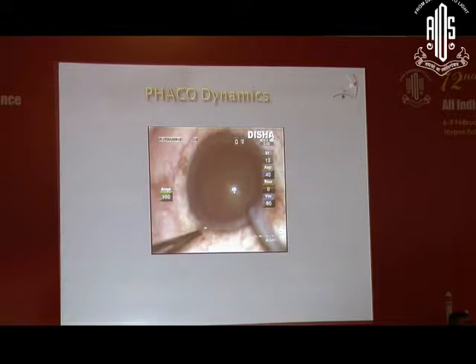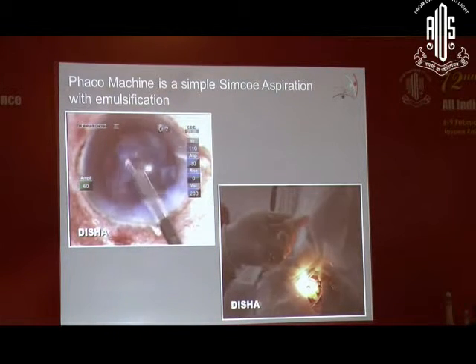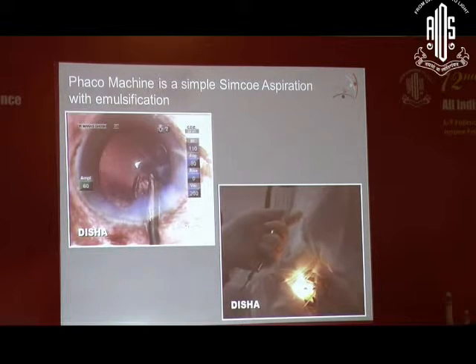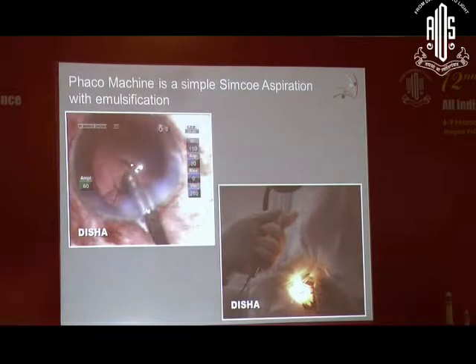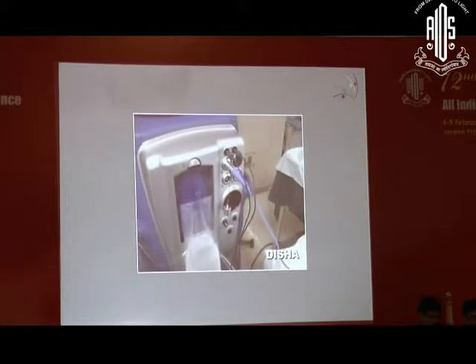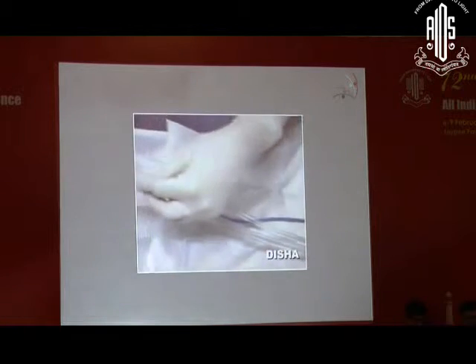The third area that I would like to take up with you is phaco-dynamics. We need to understand a little bit of this. Without complicating things, it is just an irrigation aspiration system where we have emulsification or ultrasound for harder things which we cannot aspirate. So this depends upon a gravity-fed passive fluid system, which is the infusion, and this is the phaco machine that houses the motor, and this is the cassette, and this leads to a blue wire which takes the electrical signals to the ultrasound, and two tubings for the aspiration and irrigation up to the handpiece. So this basically is the instrument that we need to work with.